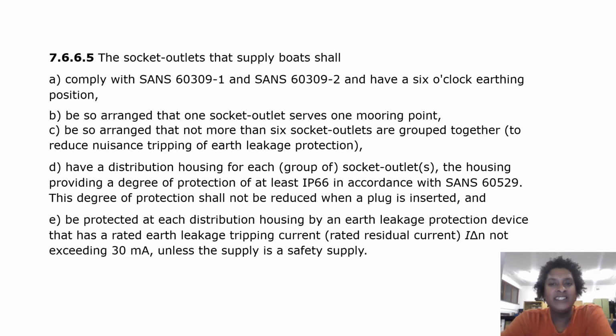The socket outlets that supply boats shall comply with SANS 60309-1 and SANS 60309-2 and have a 6 o'clock earthing position. They shall be so arranged that one socket outlet serves one mooring point, and so arranged that not more than 6 socket outlets are grouped together to reduce nuisance tripping of earth leakage protection. They shall have a distribution housing for each group of socket outlets, the housing providing a degree of protection of at least IP66 in accordance with SANS 60529.